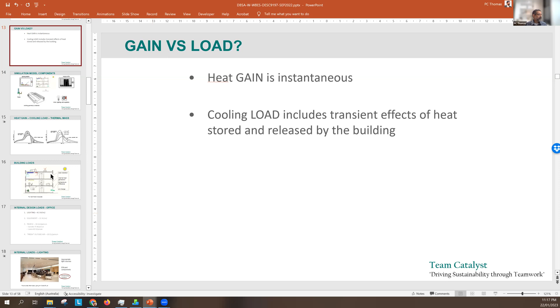They translate to cooling load in a slightly different fashion. We talk about this like a fast Fourier transform, where you put in a pulse of heat gain and then watch the decay of that heat gain across time, and that's what the air conditioner has to meet. So that's what you're doing when calculating cooling loads. In energy simulation, you specify the elements that provide heat gain, all the things we saw in that graph, and then the program computes the cooling load. So let's go straight into Design Builder.